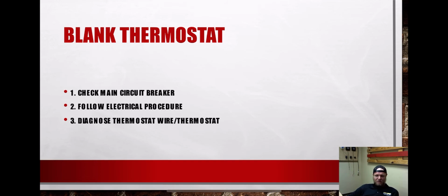So turn that disconnect off, go downstairs, turn that breaker on, go back upstairs, make sure your gauges are on it, your amp clamps on it, make sure your thermostat wires are pulled off, and you want to jump everything out one by one when anything trips the breaker. It's always good to be safe, stand out of the way when you start things up, things like that.